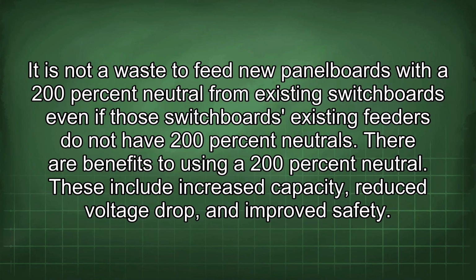It is not a waste to feed new panel boards with a 200% neutral from existing switchboards, even if those switchboards' existing feeders do not have 200% neutrals. There are benefits to using a 200% neutral. These include increased capacity, reduced voltage drop, and improved safety.